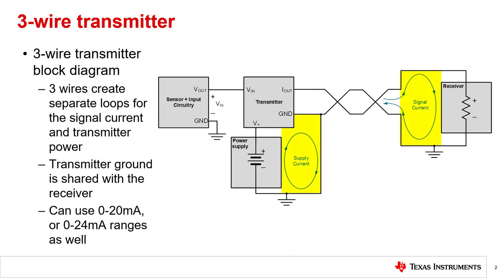The supply current and signal current are in two separate loops. This allows the transmitter to interface with inputs that need to be ground referenced. Because the output signal doesn't include the current consumed powering the sensor and transmitter, the output can go down to 0 milliamps. This allows the designer to use the common 0 to 20 milliamps or 0 to 24 milliamp output spans as well.